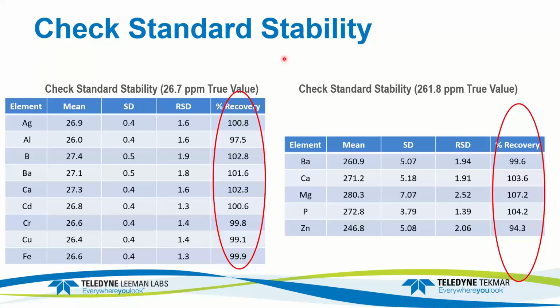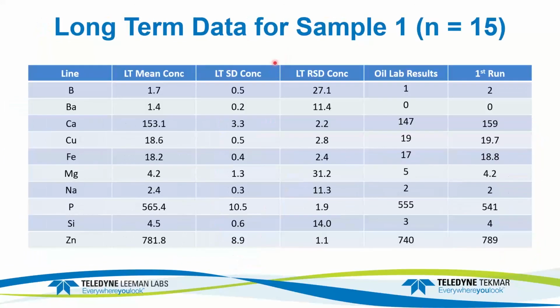Because of the higher speed with this approach with the ASX Express, we actually ran more samples in the same amount of time. In this case, this was the sum of 15 readings of the check standard. You can see overall over the 2 hours or so, or 2.5 hours, that the RSD of the standards, the descriptive statistics, everything was less than 2%. So stability is quite good. Accuracy was the same as it was in the standard analysis.